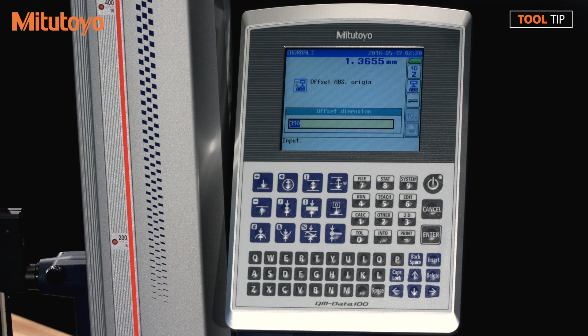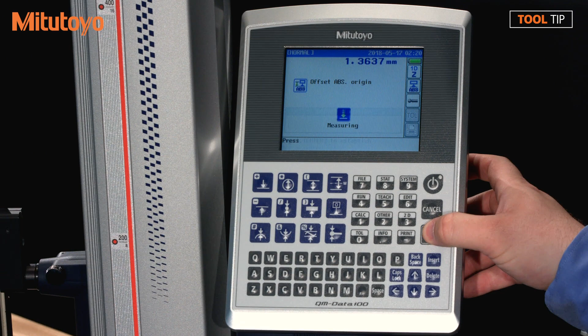So the first thing I'm going to do is hit the datum button on the front of the screen, and then I'm going to select option number 4, which is a preset. So to continue, I'm going to hit enter. So the measurement's been made, and now the display wants to know what the offset value is. So it's a 390 position on the Checkmaster. Now what you want to do to be sure is take your certification for the Checkmaster and make sure that you put in the exact value. And it's probably not going to be 390, it's probably going to be 390 and then a bunch of decimal places. So make sure that that accurate value is put into this box. Once you're satisfied, go ahead and hit enter to accept the changes.